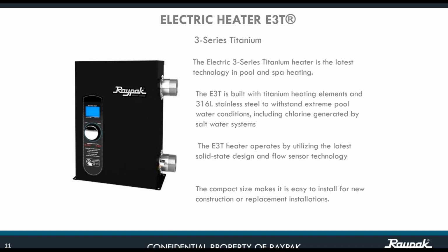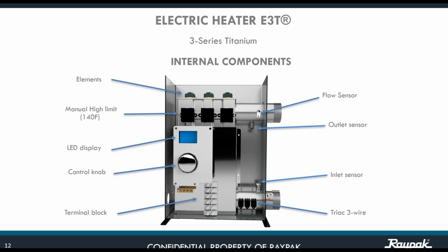No more contactors, now it's solid state and flow sensor technology. Okay, as you see right there, internal components for the unit. This is a pictorial for a 27 kilowatt. You can see on top the whole chamber for the elements. Well, the elements 1, 2, 3. Manual high limits. That is the only safety that you might have. That is rated to 140 degrees.